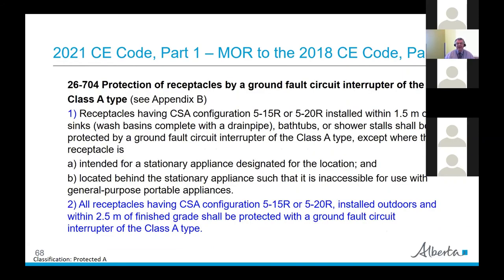Also in Section 26 — another eyebrow-raiser: all receptacles having CSA configuration 5-15R or 5-20R installed outdoors and within 2.5 metres of the ground shall be protected with a ground fault circuit interrupter, Class A type. So now parking lot plugs and similar outdoor receptacles that didn't previously require GFCI protection will require it starting in the 2021 code, coming into force in Alberta in 2022.